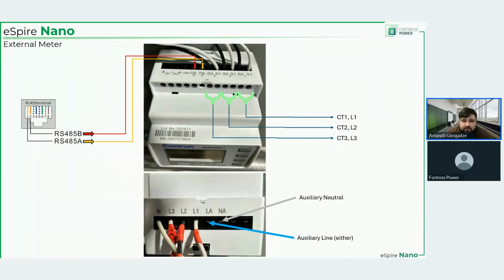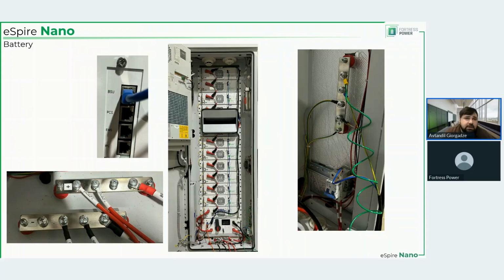Now, we spent a ton of time around the inverter, but as I said, the inverter is more complex in its interconnection principle, whereas the battery, which you see right here, and I apologize for the amateurish photos that were taken in the lab. This kind of shows you that we are actually working on this thing. The battery itself comes pre-assembled. All you need to do is connect the DC cables from the inverter to the battery. Let me see if I can get my laser pointer here. Right here. So this is where the battery would connect to the inverter.